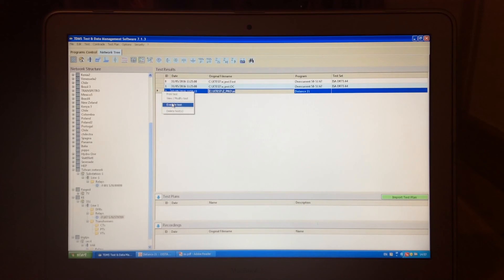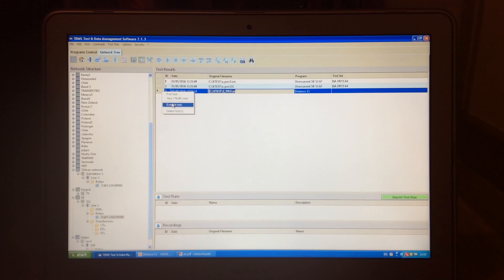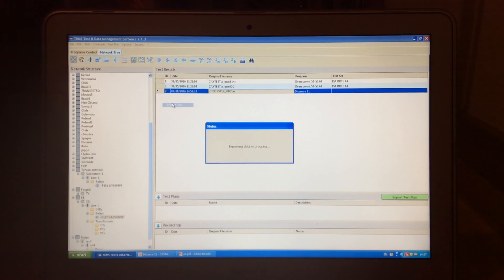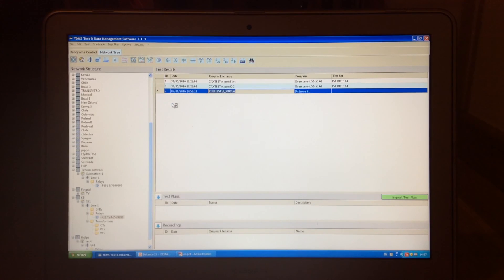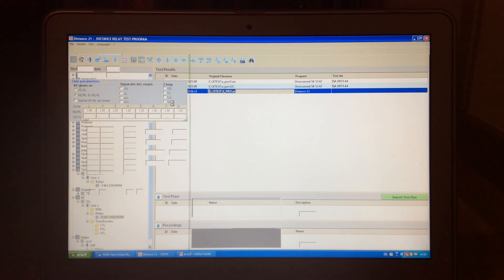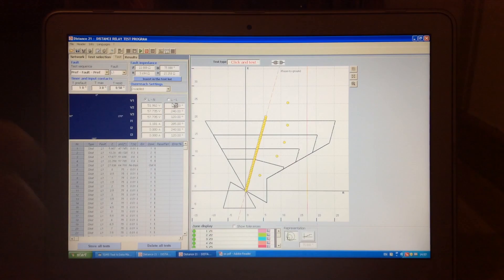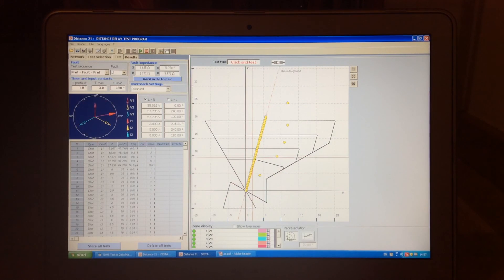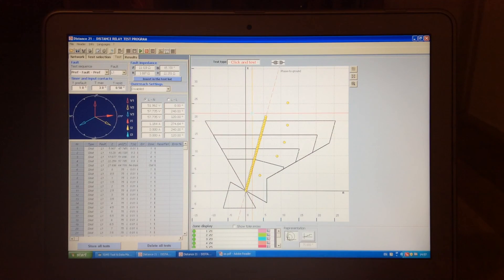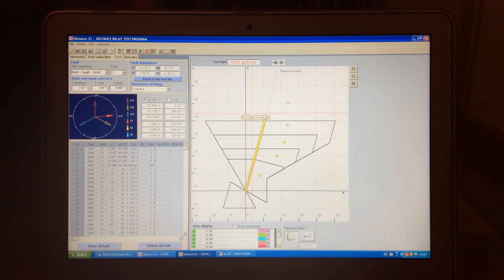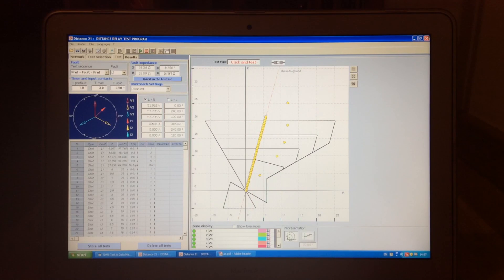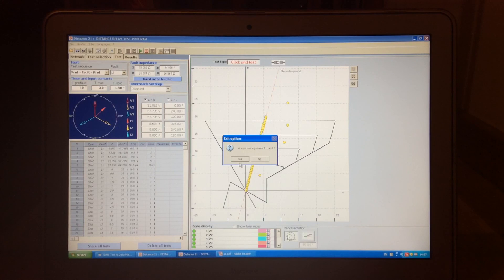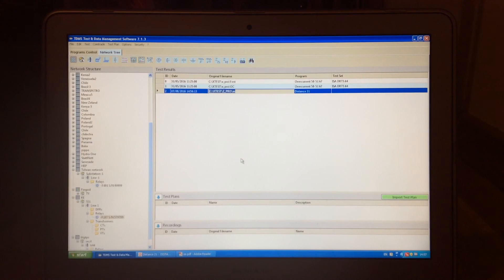So, every time you come each year to do the same test, to test the same relay, you can do the same test actually, and you just press execute test, and it will open the same application with the same testing points. You'll just see that they're all yellow right now, because they haven't been done. So, this would be the distance protection, and we'll continue later with differential protection.